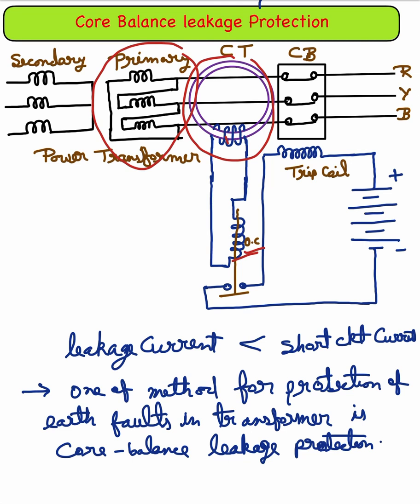There are two situations to consider: normal condition and fault condition. Under normal condition, when no earth fault occurs, the sum of the currents of the three phases R, Y, B is always zero, and there is no resultant flux in the core. No matter how much the load is out of balance, no current flows through the relay operating coil, and the trip circuit remains open.